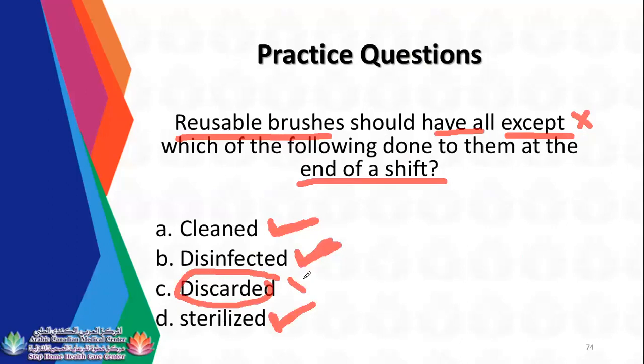But when can you discard reusable brushes? So the except is actually letter C, discarded. When you can discard reusable brushes. So at the end of the shift, it's either you will clean, disinfect and sterilize, or you will clean and disinfect only and not sterilize, as long as at least it is disinfected. Your disinfection will be useless if you are not cleaning your brushes. Your sterilization will be useless if you are not cleaning your brushes. So clean first, then either disinfect, or disinfect and sterilize. There's no issue with that.